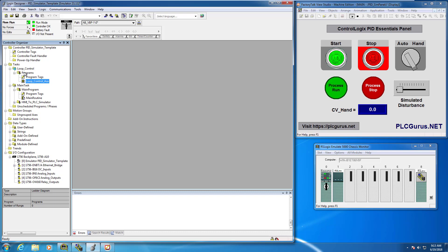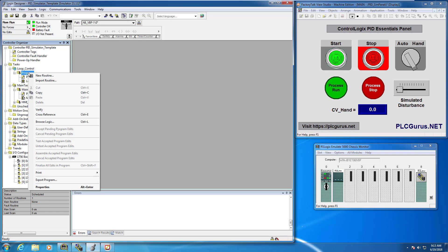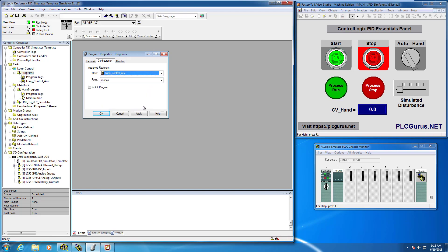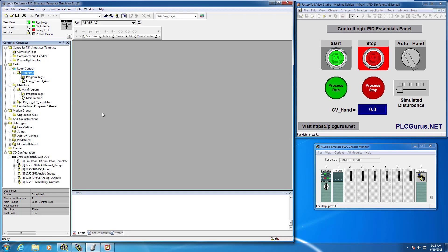Remember, the CPU only scans one routine in each program. In the main task, the main routine is identified by the little sheet of paper with the one symbol. Every program needs a main routine associated. So I'll click on program properties, go to configuration, and assign 'loop control auxiliary' as the main routine for this program.